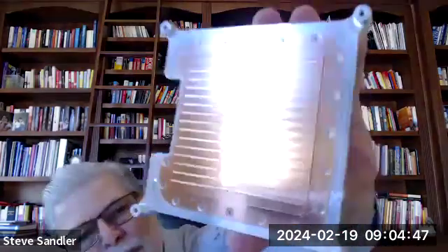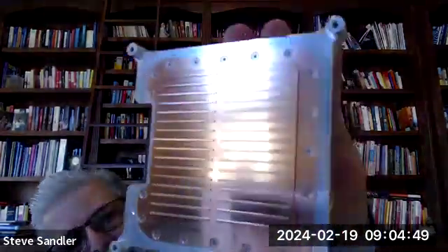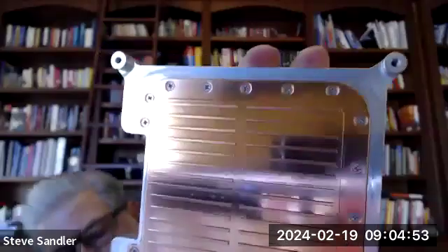We had to custom design resistors because we couldn't find resistors that could do what we needed them to do. So we designed new three-terminal resistors that have near-field cancellation in them. And we designed two-terminal resistors specifically to be water-cooled. Those are made up with a manifold that's sort of in braille, and you can probably see those channels there. Those channels are designed to lay right across our custom two-terminal resistors.